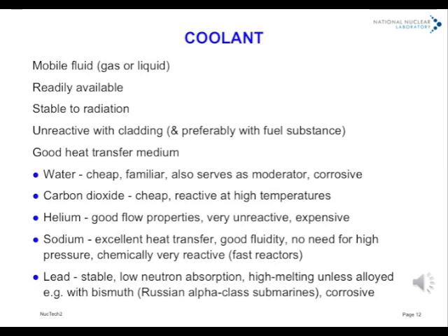Of those available, water is cheap, familiar, can also serve as a moderator, but is somewhat corrosive. Carbon dioxide is cheap, but reactive at high temperatures, and in pure form can gradually erode a graphite moderator. Helium has good flow properties and is chemically unreactive, but relatively expensive.